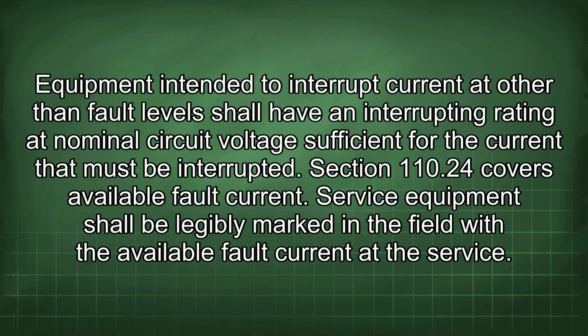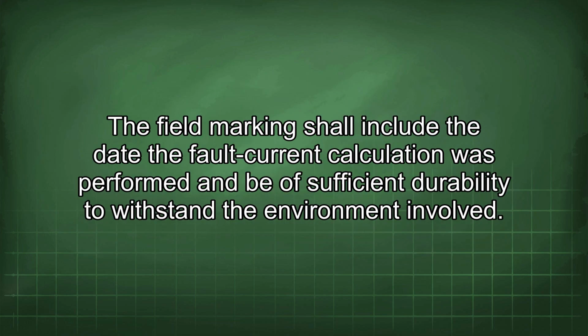Section 110.24 covers available fault current. Service equipment shall be legibly marked in the field with the available fault current at the service. The field markings shall include the date the fault current calculation was performed and be of sufficient durability to withstand the environment involved.